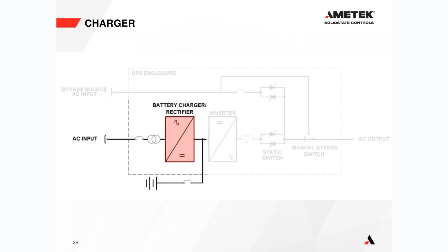Now let's go into how the charger actually does that. Here's our charger section. Its only job is to convert the AC to DC that can be stored. Every parameter of the charger is dictated by the battery. A lot of people get confused, thinking the charger has to do this, that, and the next thing because the inverter needs to do this, that, and the next thing. No - the only thing the charger rectifier has to do is keep the batteries charged at a certain voltage. That's its only job. Every parameter is dictated by the battery bank.